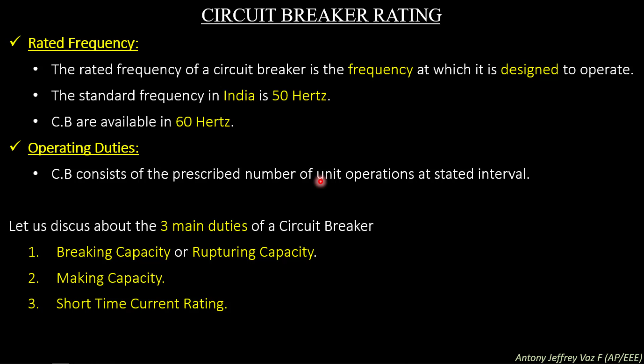And the third one is short time current rating. If a lot of circuit breakers are working together, the good circuit breaker should not trip. If the fault is occurring in another part of the circuit or area, then only that area should trip. The circuit operating in the good area should not trip. So this is the short time current rating of a circuit breaker.